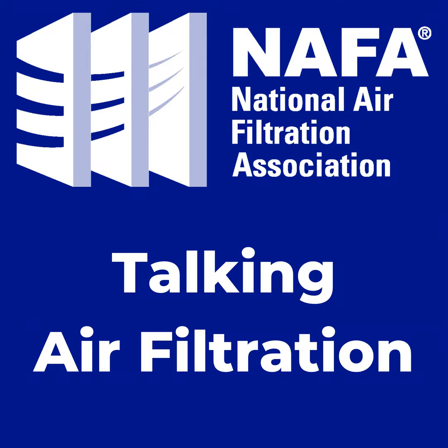We see the dust reports, and we know that ASHRAE dust is what we have for the testing. But I've not heard someone say that this nanofiber media has 4 grams of dust holding capacity, but they're not changing out their filter every day or every week when they use it in application. The filters are perfectly fine to use for a normal life cycle of a filter, so they're not seeing the type of dust loading that we do in a test. ASHRAE dust is really unfair to nanofiber medias, I think, is what it ultimately comes down to.